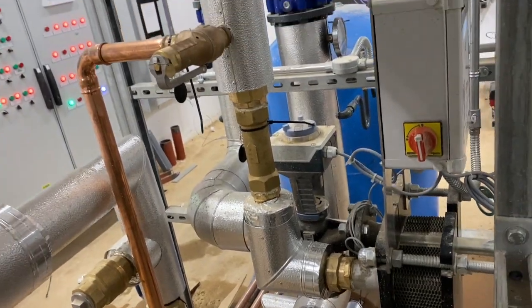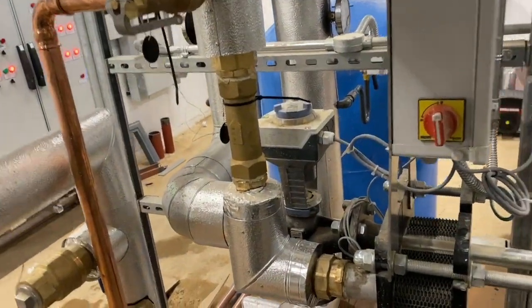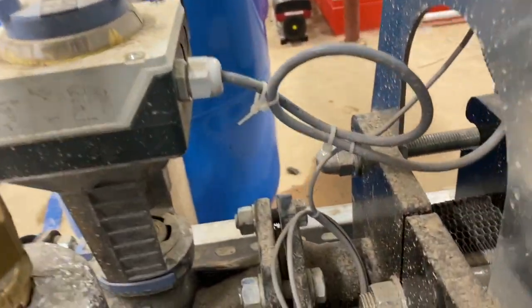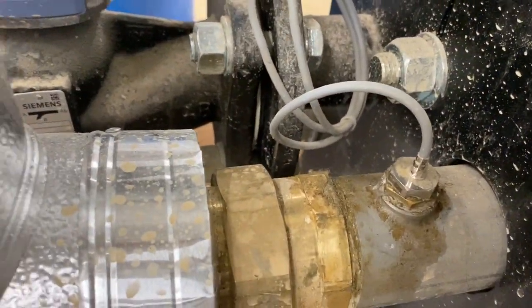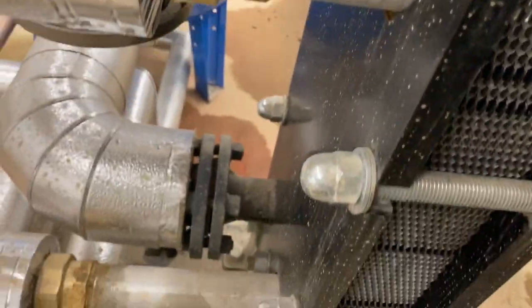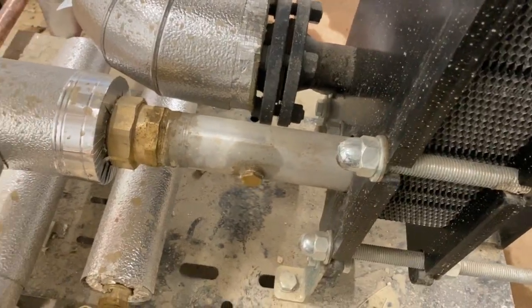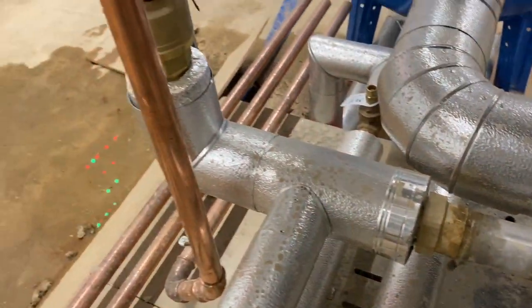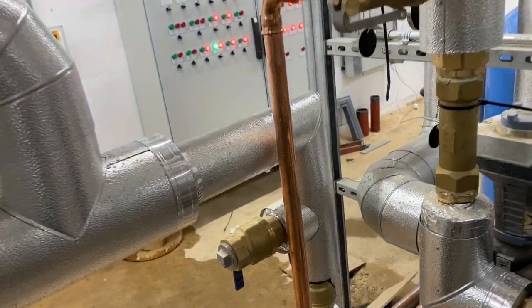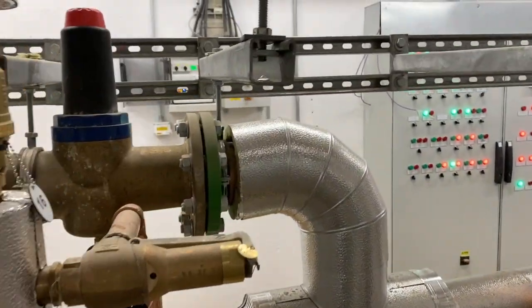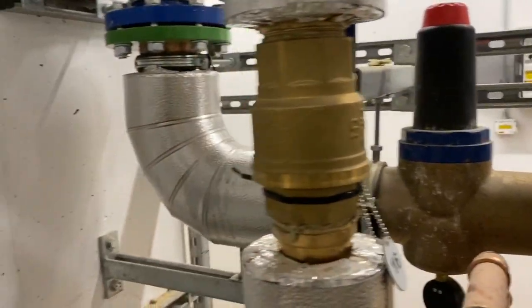Typically that number turn on the outlet wouldn't be there. Three-way valve, which is by Siemens. This with the sensor is where that is always the hot outlet. So that PT1000 sensor is that outlet. We're showing the inlet now, working backwards towards the cold. It's just an unusual setup on this particular installation.